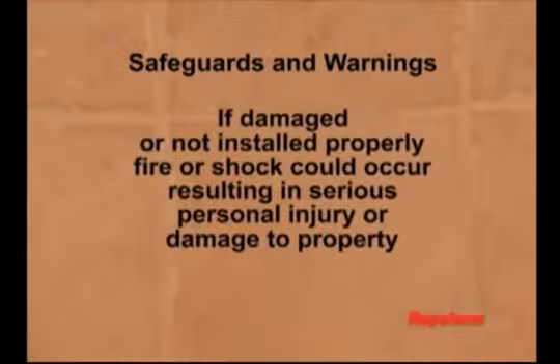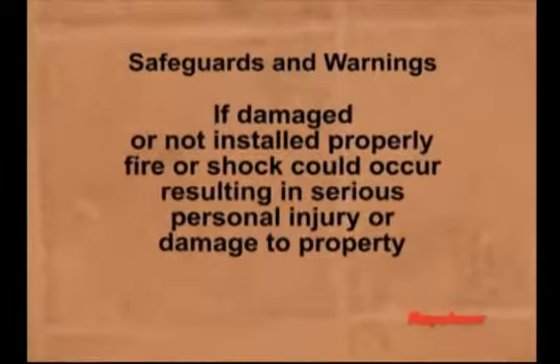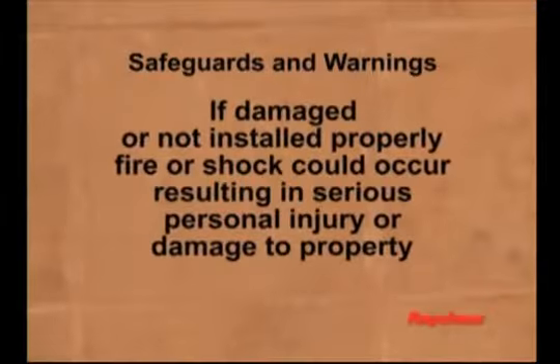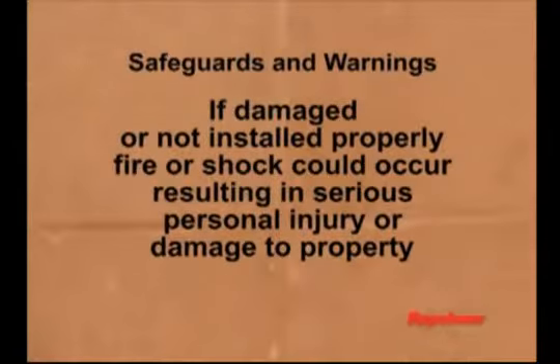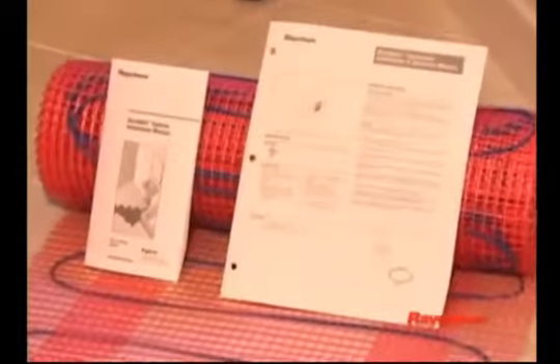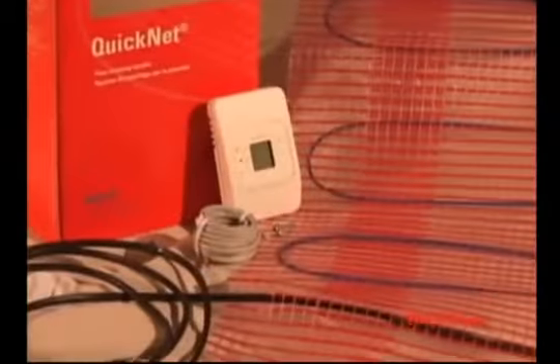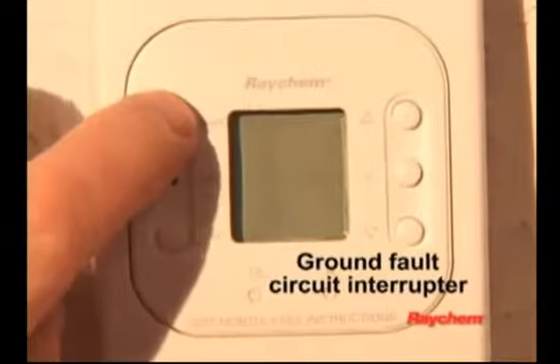If the QuickNet mat is damaged or not installed properly, fire or shock could occur, resulting in serious personal injury or damage to property. Follow these warnings and instructions. The QuickStat thermostat must be used. It has a ground fault circuit interrupter to prevent electric shock.